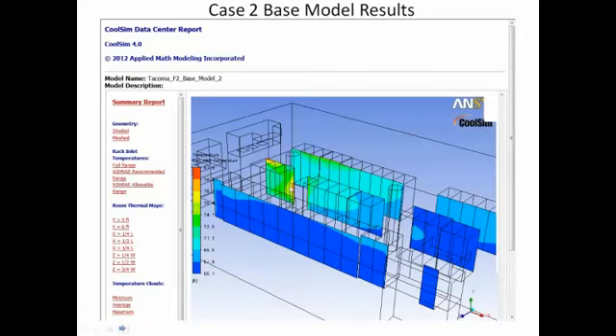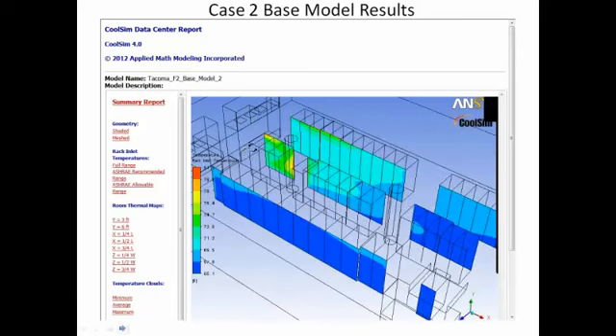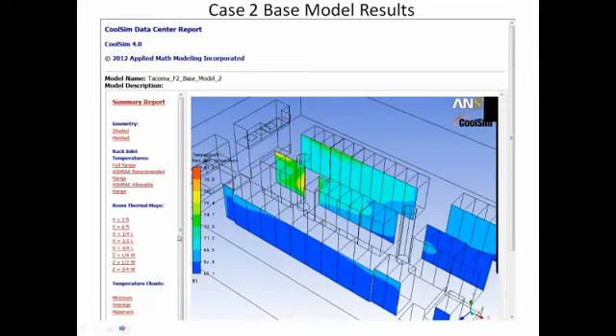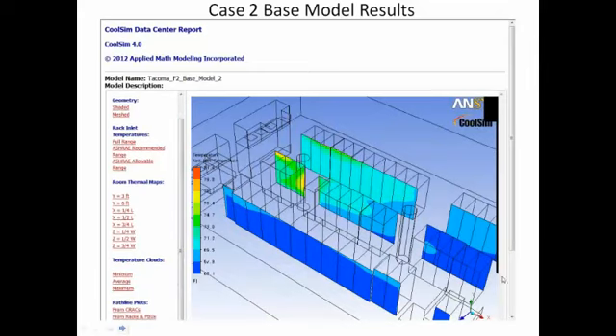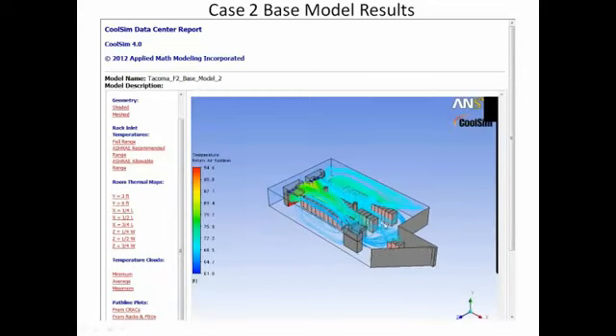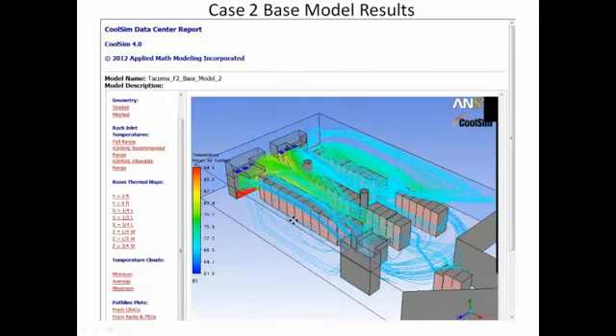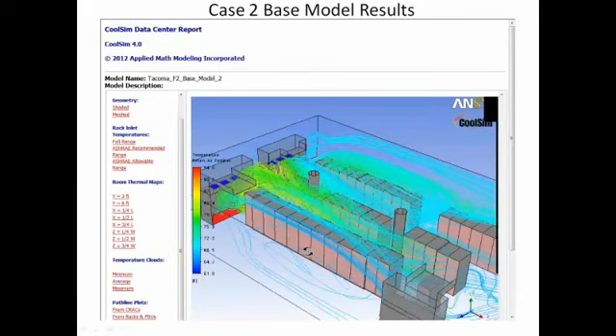And I often find this. I find that the units closest to the CRAC units are the hottest because the air is rushing by in one direction or, in this case, is also being sucked back to those inlets. Returns. The returns are at the bottom. So let me show you that here in one of these plots. Here I'm going to look at path lines, which are sort of particles in the air that are coming back to the cooling units.